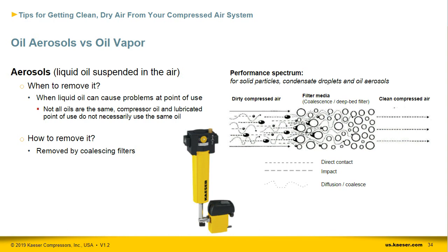Oil aerosols are removed by coalescing filters. These filters cause the aerosols to coalesce into larger drops inside the filter media. The drops then fall off the filter element into the bottom of the filter housing.